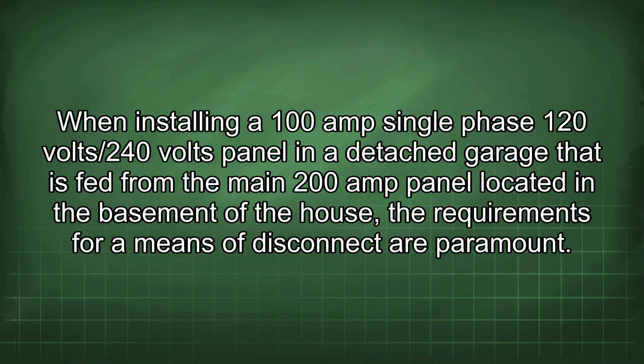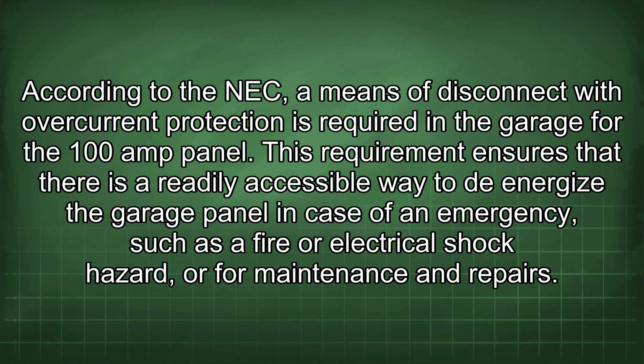When installing a 100 amp single-phase 120 volts/240 volts panel in a detached garage that is fed from the main 200 amp panel located in the basement of the house, the requirements for means of disconnect are paramount. According to the NEC, a means of disconnect with overcurrent protection is required in the garage for the 100 amp panel. This requirement ensures that there is a readily accessible way to de-energize the garage panel in case of an emergency, such as a fire or electrical shock hazard, or for maintenance and repairs.